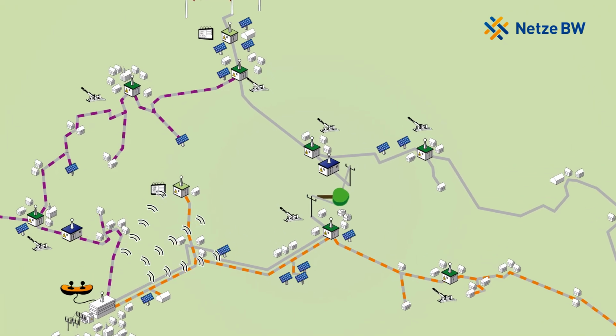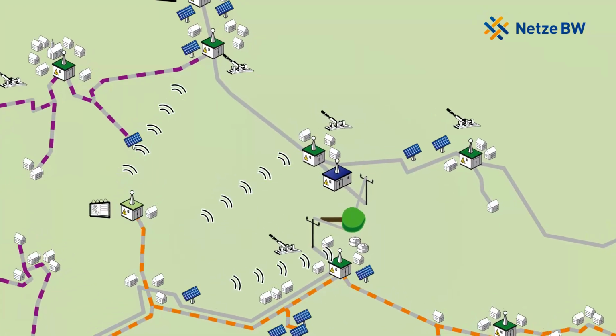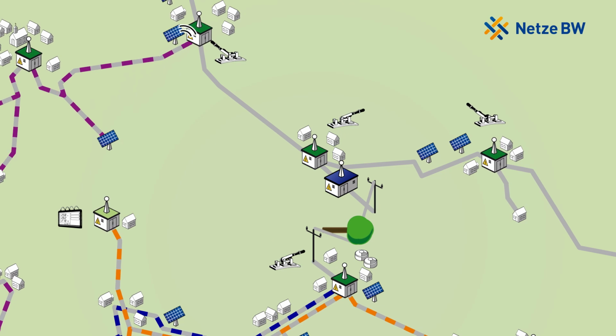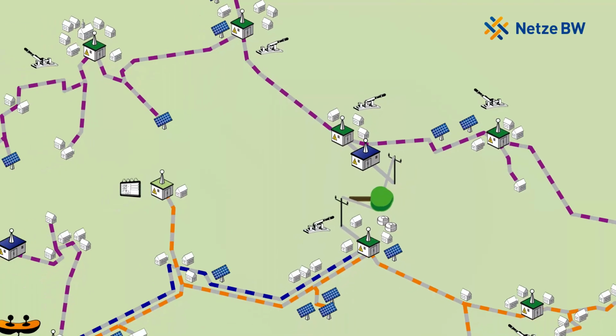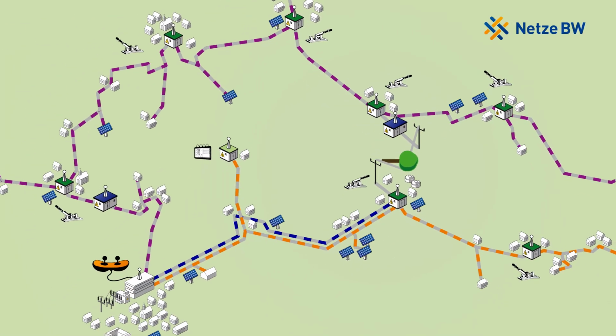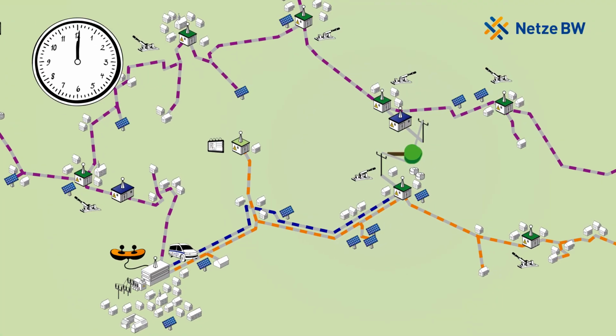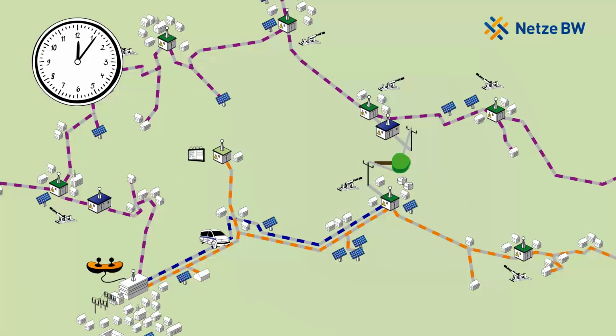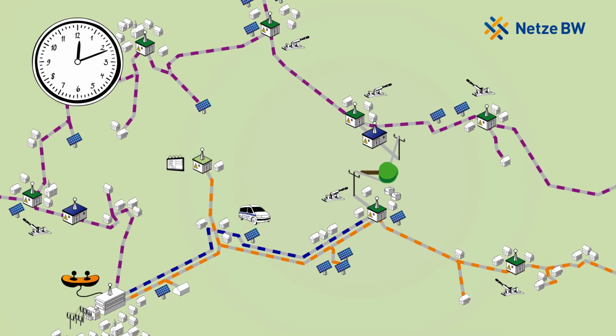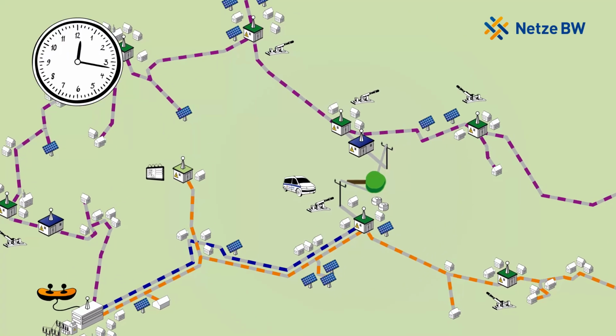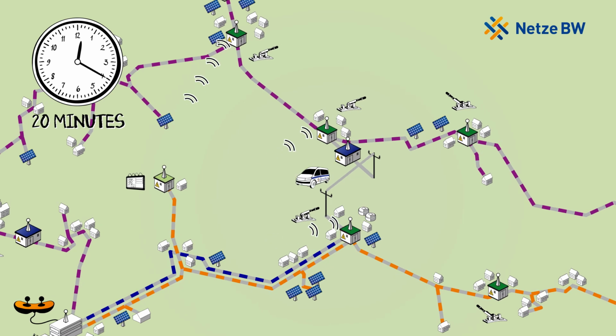The switches in the various intelligent distribution substations are then regulated by the regional controller to establish the grid configuration previously calculated. Power failures can in this way be limited within a very short time to a very small section of the grid, which the Netze BW technicians can then target and repair.